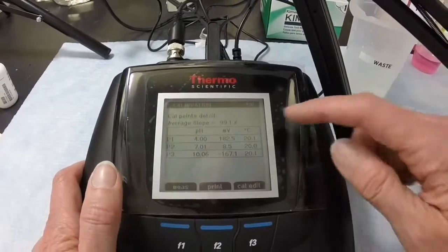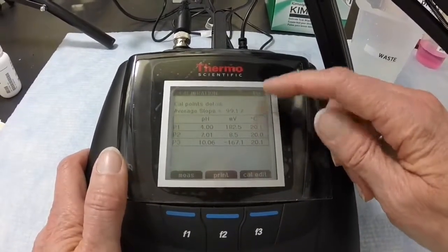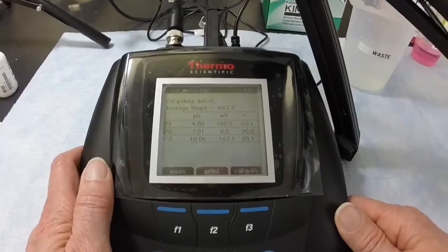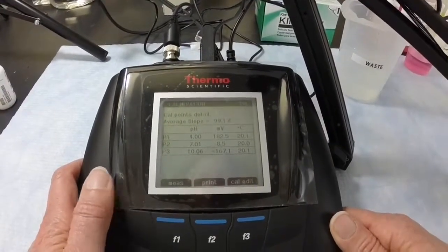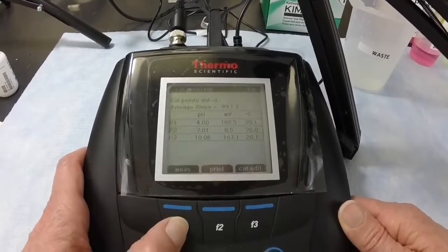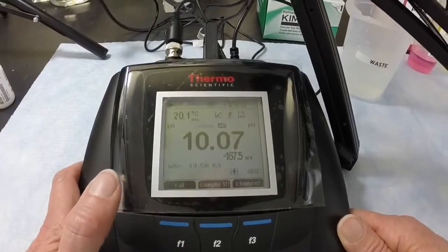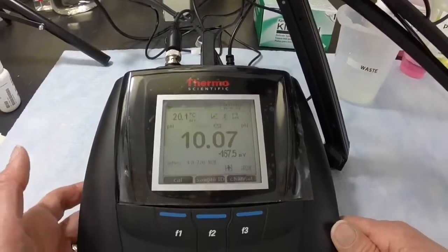The average slope will display at the top of the calibration table. We have a slope of 99.1%, which is great. So we're all done. We press Measure, and we return to the measure screen. We are ready to make a pH measurement.